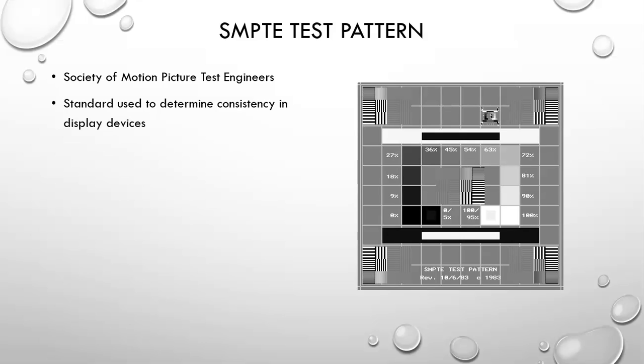The SMPTE test pattern was made by the Society of Motion Picture and Television Engineers, and this provides a standard used to determine the contrast, brightness, and resolution of displays. On most of our machines, there's a way to pull up a SMPTE test pattern, and then you just look at it on the display and see how faint of a line you can see, that's how narrow together it is, and you check that to what you saw 6 months ago, and that tells you if there's been any changes.